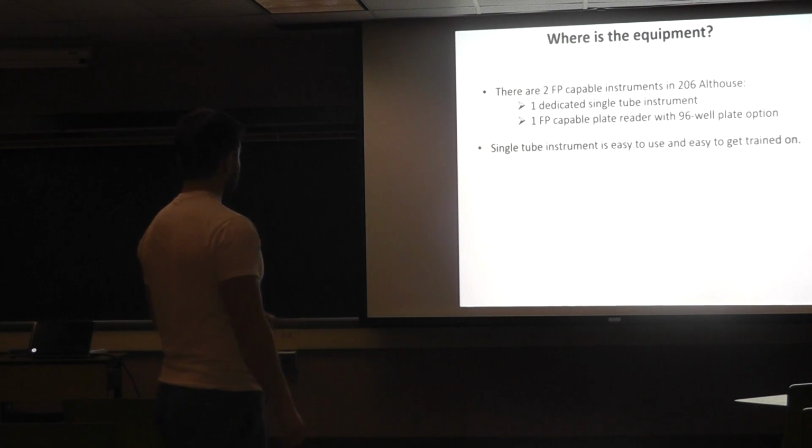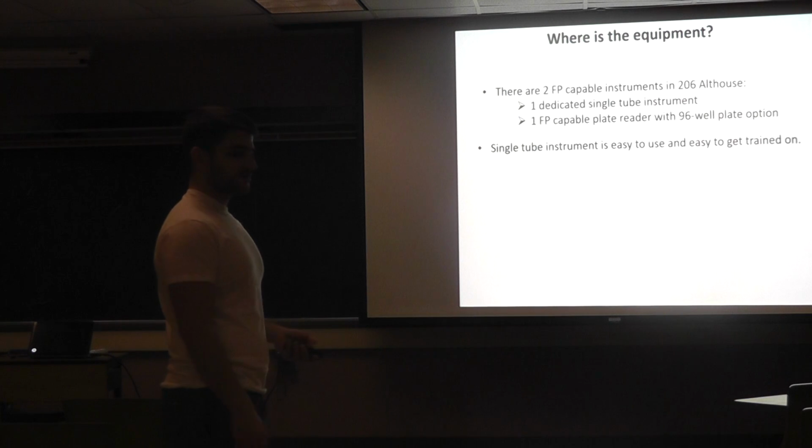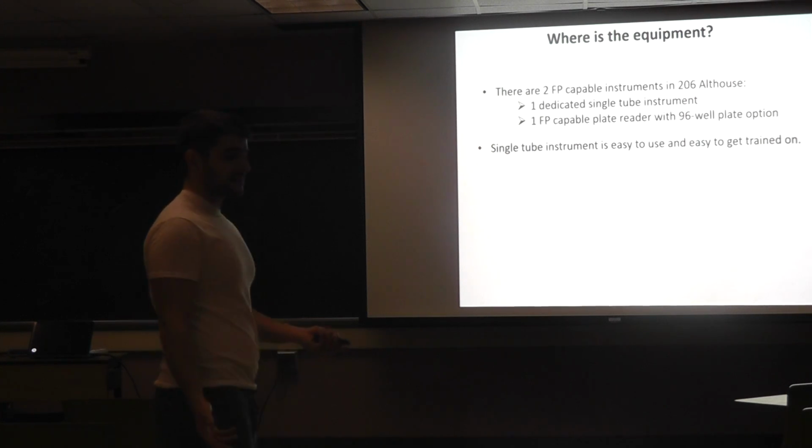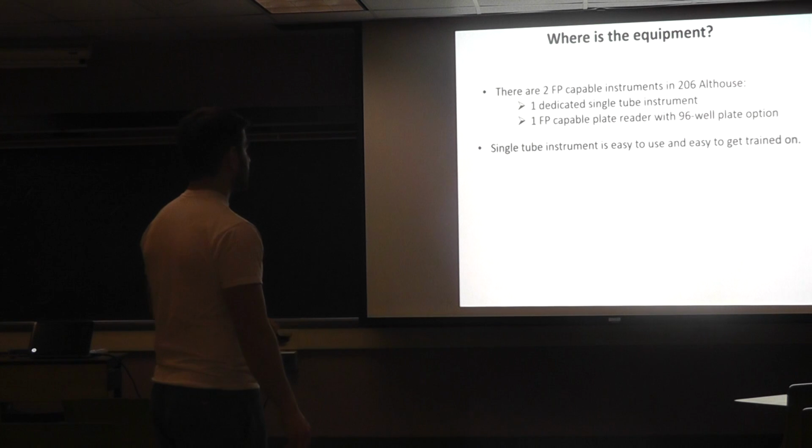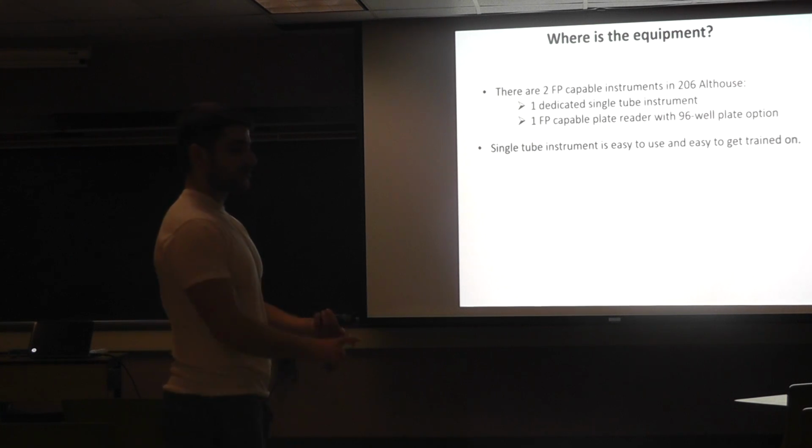Anyway, the single tube instrument is easy to use, and it's really easy to train someone. You just need to tell them which protocol to use and how to handle things. There are not too many settings that you need to worry about. You can create your protocol: what temperature you want to use, how many measurements, whether you want static versus kinetic measurement, and the equilibration time. That's pretty much it, and then you're set to go.